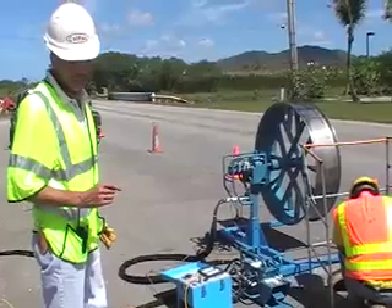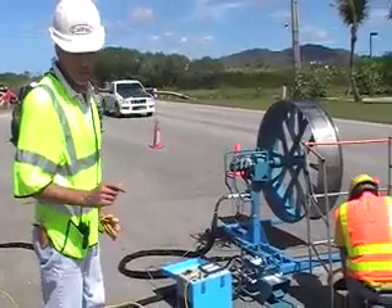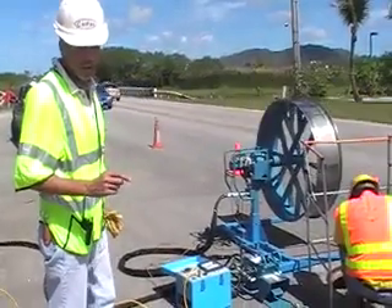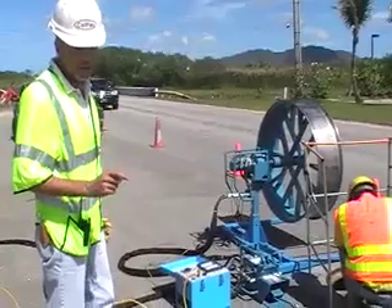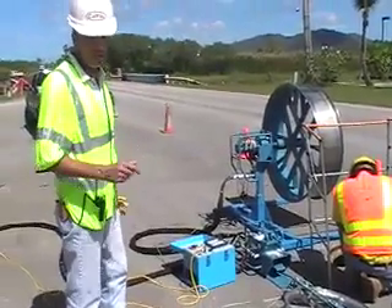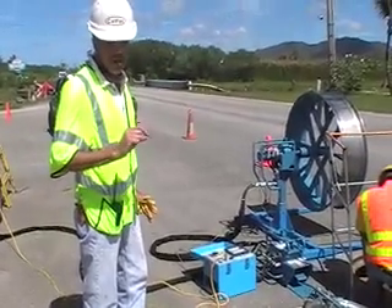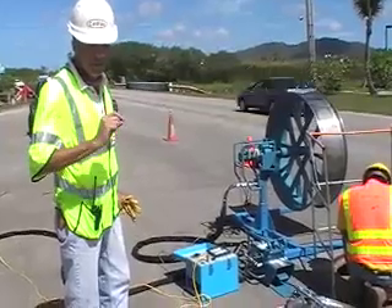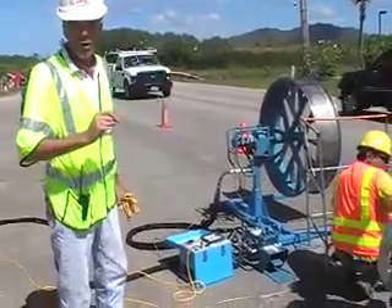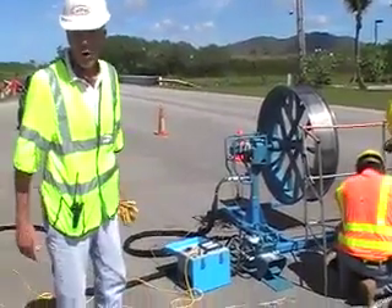We have a secondary protection device, and that's called a breakaway swivel, which is provided to us by the customer in this particular case. That device goes right on the Kellems grip, which grips the cable, and then is attached to the pulling rope. That device has little pins in it, and those pins are designed to break at below the manufacturer's recommended pulling power. So there's a second failsafe, if you will.